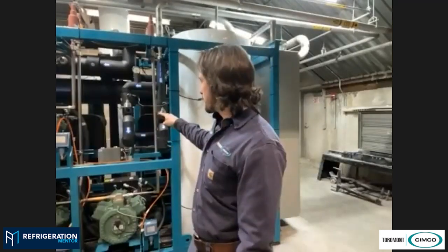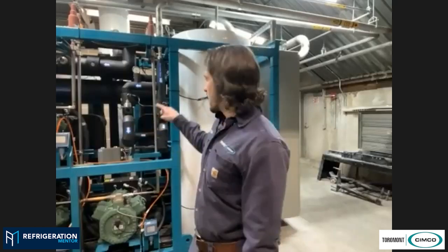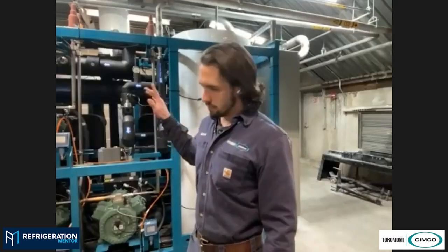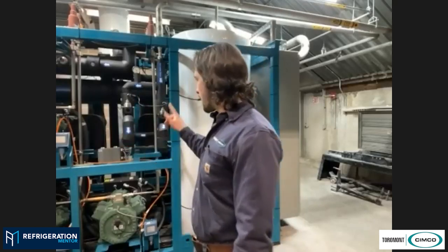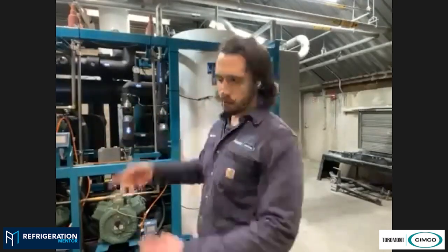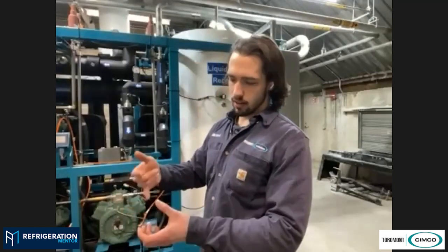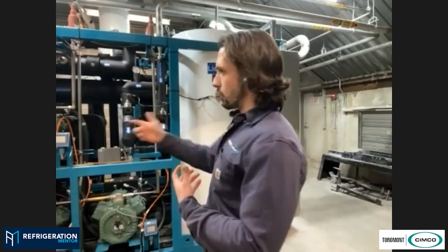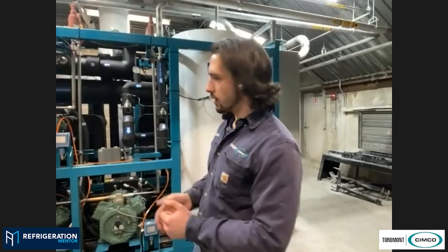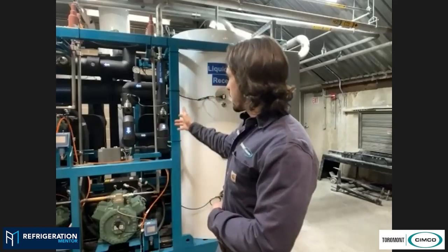Here we have two parallel HPV valves. That issue I spoke of earlier, having two HPV valves is a blessing, having that redundancy, because that was actually the point of failure we had. The strainer that came with it was punctured and one of the valves became contaminated, and we actually had to load shed and run it off one, which we were able to do, which is pretty amazing for it being summer when we had that issue.